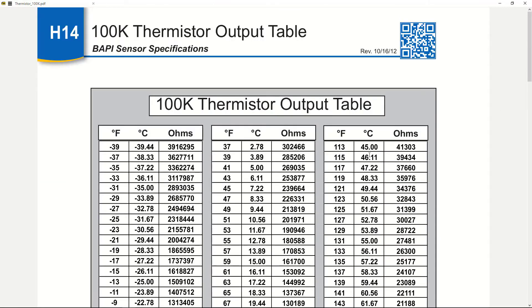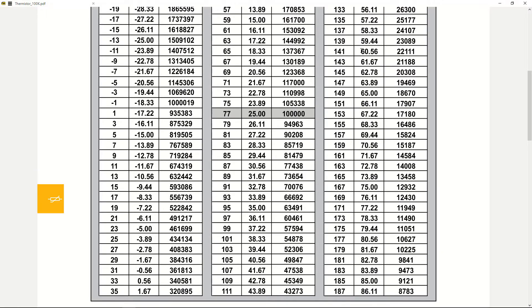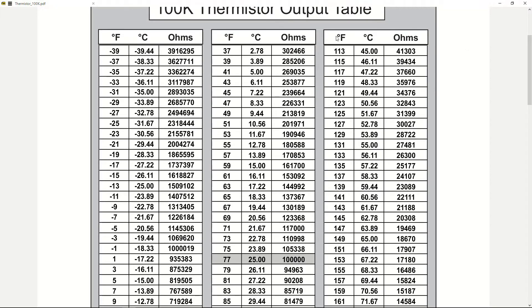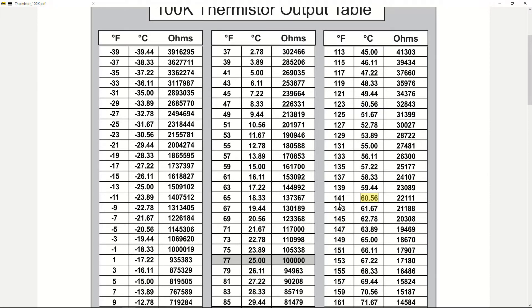Let's come to the data table and look for 60 degrees, since we want to turn our fan on at 60 degrees. There it is — making sure these are degrees Celsius: 60.5°C, roughly 60 degrees, equivalent to 141 degrees Fahrenheit. The thermistor resistance equivalent to 60 degrees is 22.1 kilo-ohms, that's 22,000 ohms.